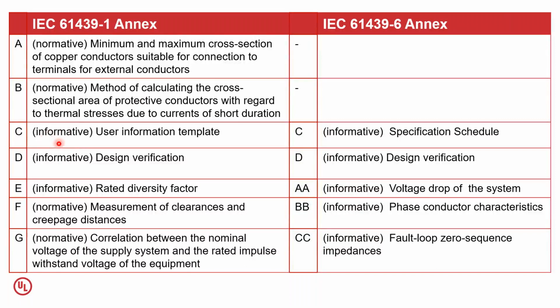Now the reason that this is being made informative is that every user can have a different way of defining things. For example, they may want a different short circuit level, a different IP rating, or a different fire rating. So in that context, you will notice that this has been made informative in this case. Similarly, you will also find informative for the design verification.